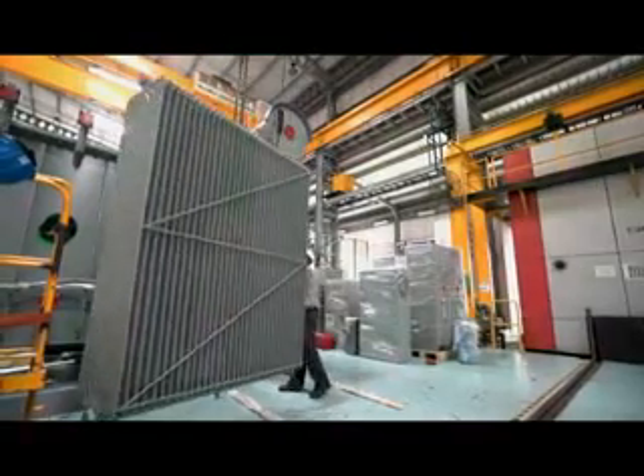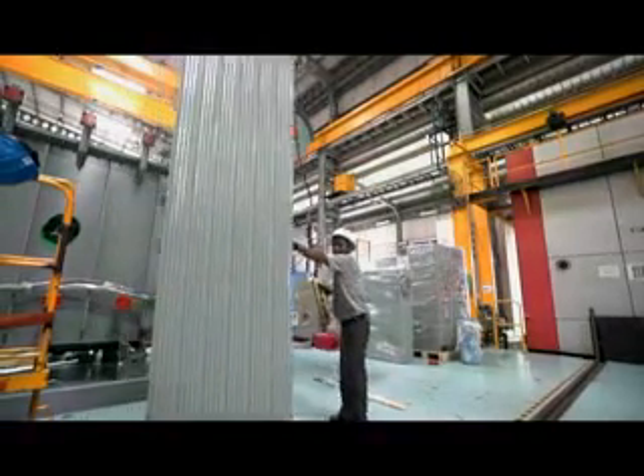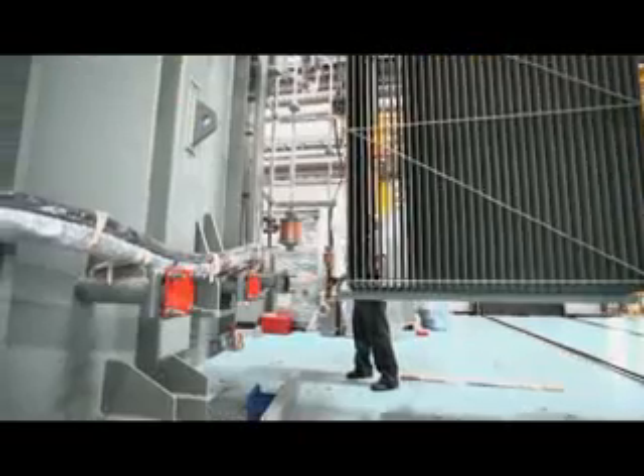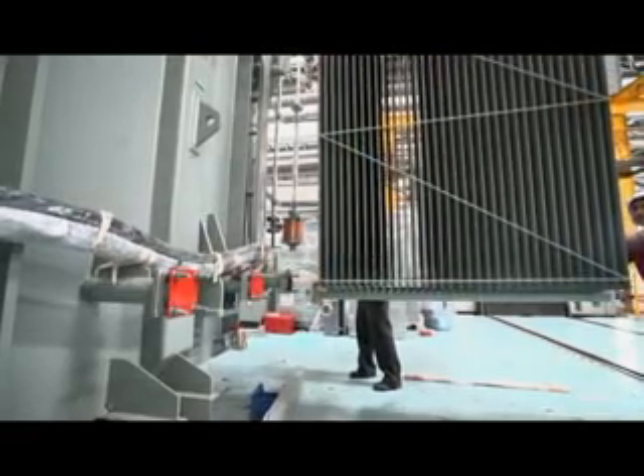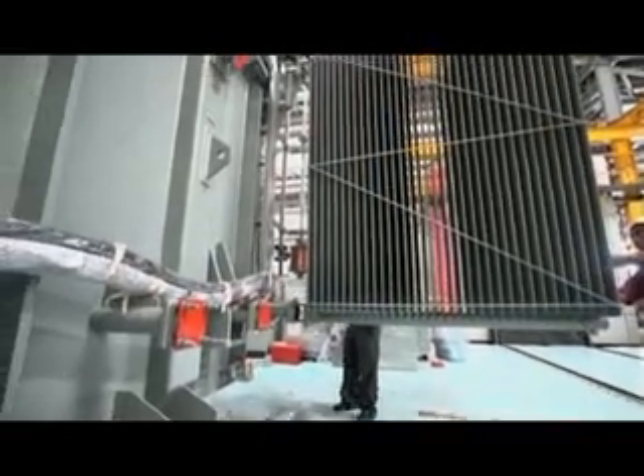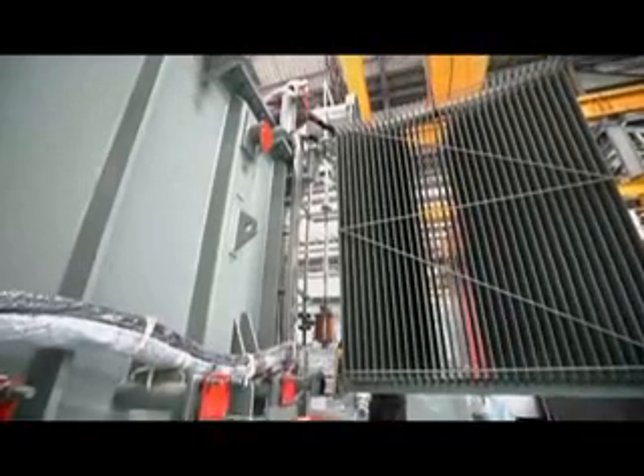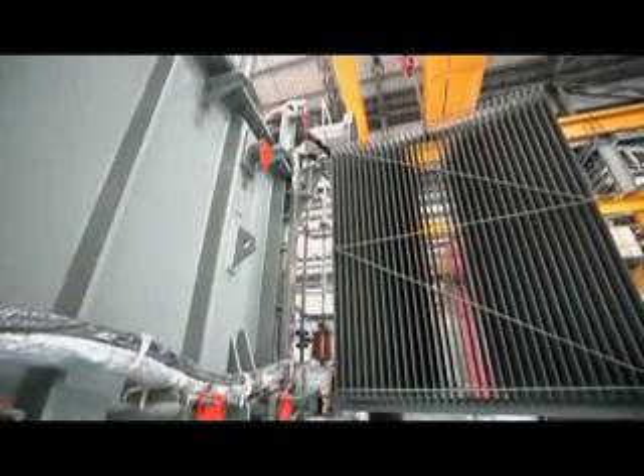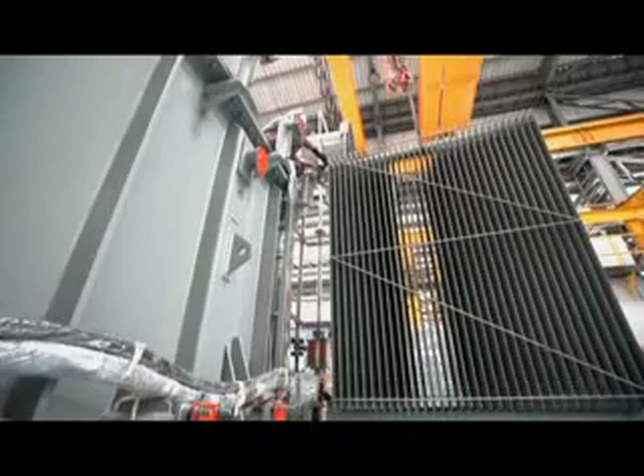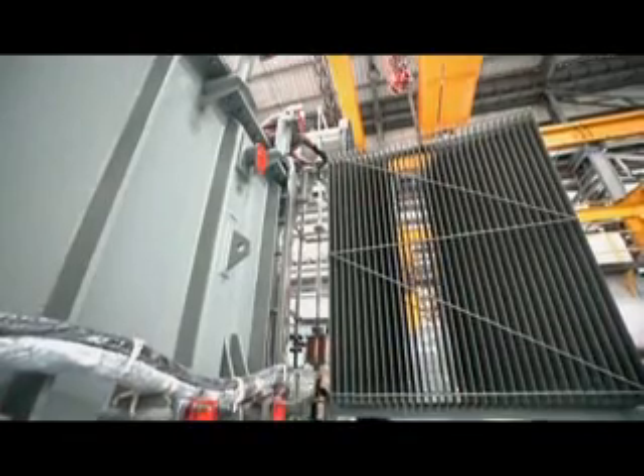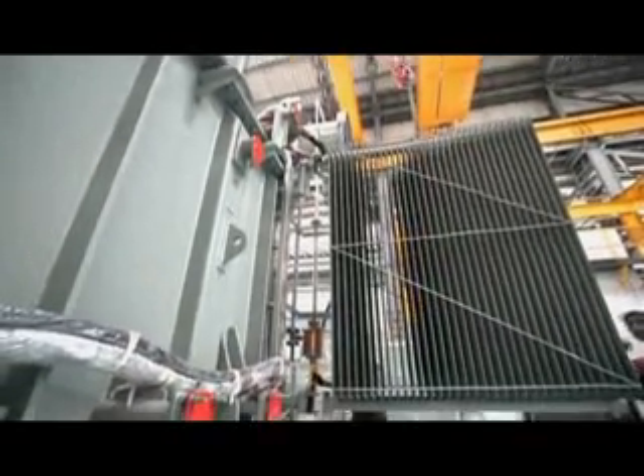In case of an electrical power transformer, due to transport limitation, these units are sent separately and assembled at site with the transformer main body. At the time of dispatching, the flanges of the radiator are blanketed by gasket and blanketing plates. The radiator valves on the main tank are also blanketed by gasket and blanketing plates.